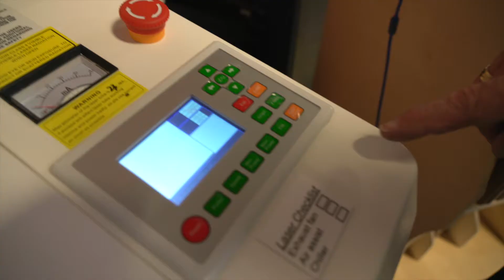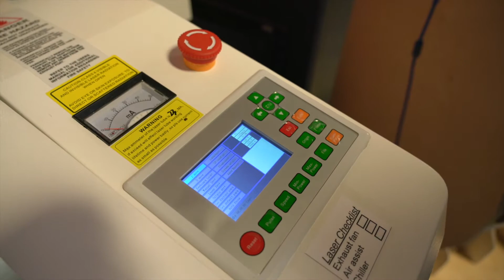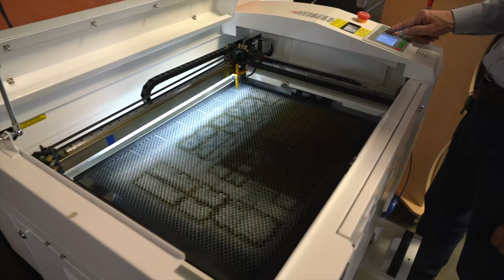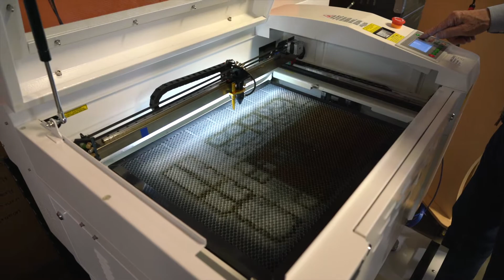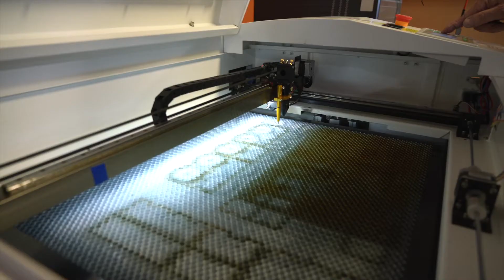You should start most commands by pressing the Escape button to exit any prior operation that may have been started. Note the compass pattern on the control panel, where you will find several buttons which control the motion of the laser lens assembly. Here we are using the left, right, up, and down buttons to move the lens assembly. This can be done while the lid is open. Be careful not to reach into the laser cabinet while any of the machine parts are in motion.